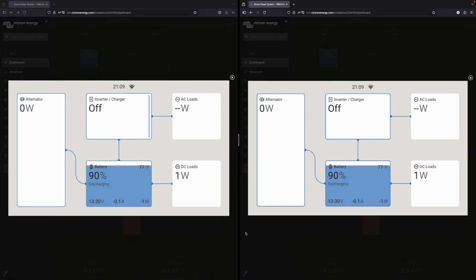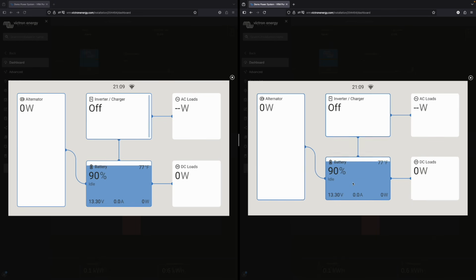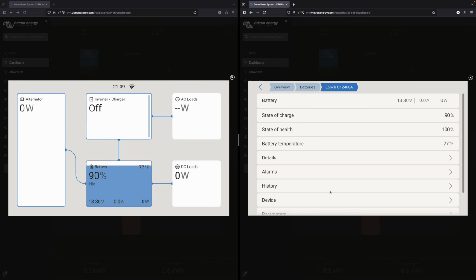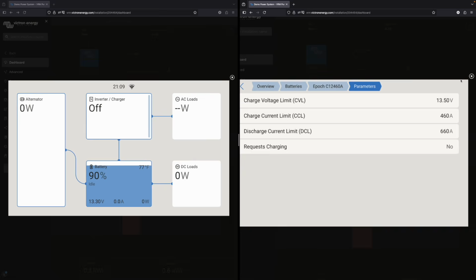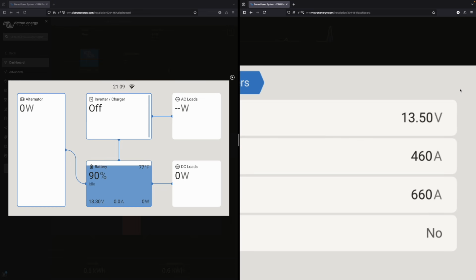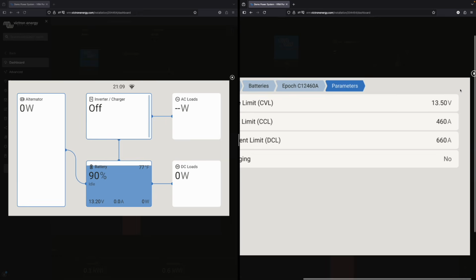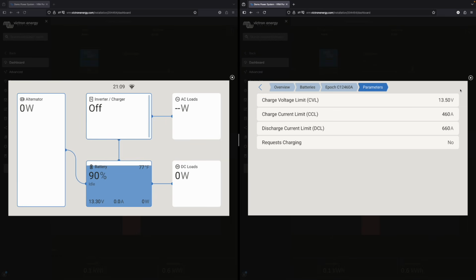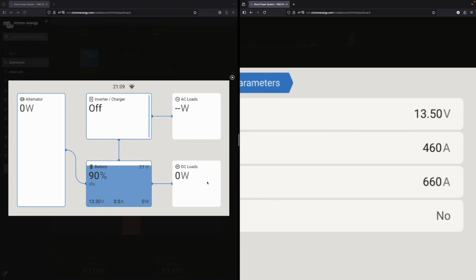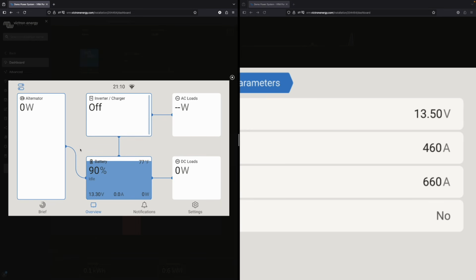Here we are in the VRM portal. I have two different windows open, and I want to show you how the battery parameters change as we go below 90%. You can see the battery bank is currently at 90%, and I'm going to attempt to demonstrate this. Let's look at the battery parameters over here — you can see our charge voltage is still 13.5 volts. After we charged up to 100%, the charge voltage limit dropped to 13.5 volts, and now when we run the batteries down below 90%, you'll see that charge parameter change back. So let's go ahead and turn on the inverter.